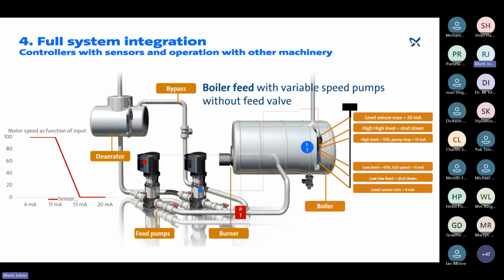So a system like this also comes with additional protections that your standard modulating valve wouldn't be able to deal with. What it can do is handle a low level alarm and a high level alarm, as well as controls for the remote water treatment of the dosing pumps. The pumps can also feature an integrated graphical display for viewing the boiler level, the pump energy consumption, and the operating hours. Faults and alarms can be viewed directly on the pumps, and they can also communicate directly back with your BMS.